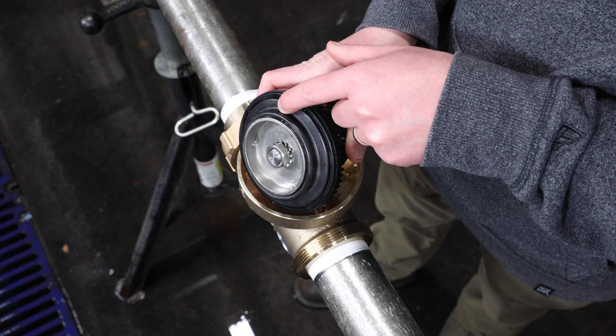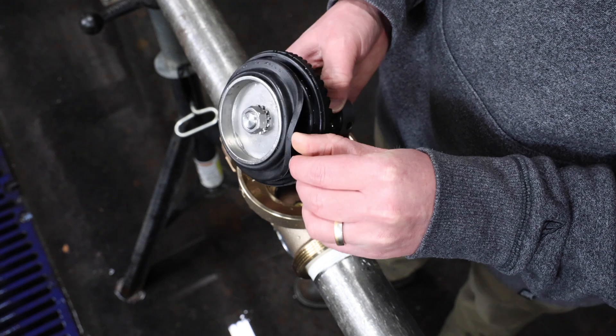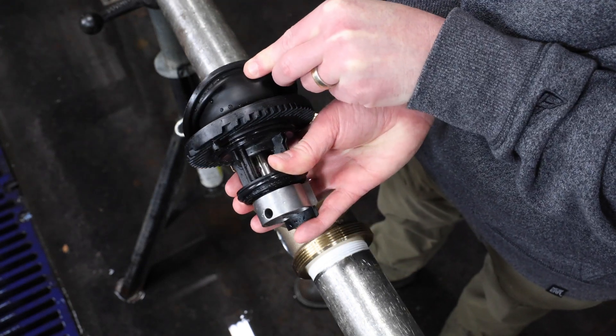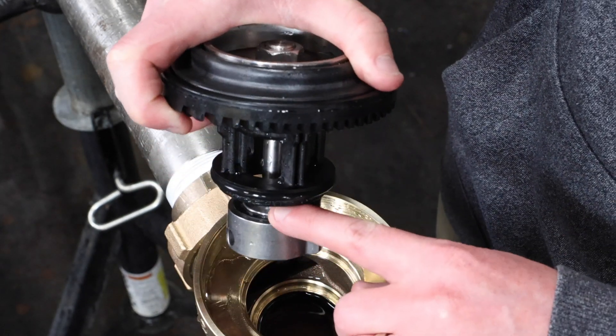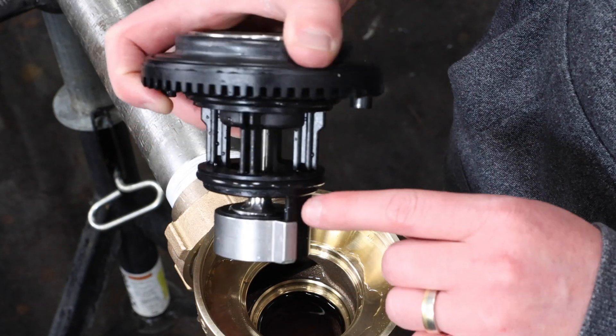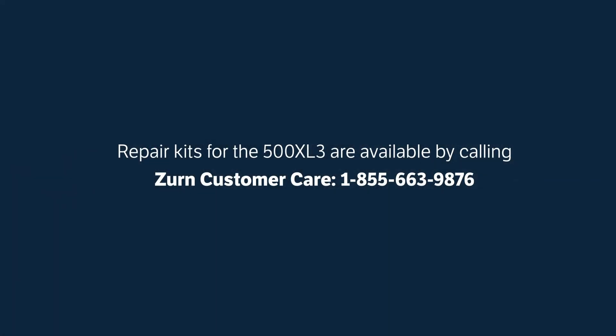Visually inspect both sides of the diaphragm for cuts, tears, or material degradation. Clean as needed. Next, inspect the seal ring and seat for any nicks, cuts, or other damage. If there is no visible damage to the body or internal parts, clean the parts as needed and reassemble according to the directions that follow. If there is visible damage to any of the parts, you will need to replace them. Repair kits for the 500 XL3 are available by calling Zurn Customer Care at 1-855-663-9876.